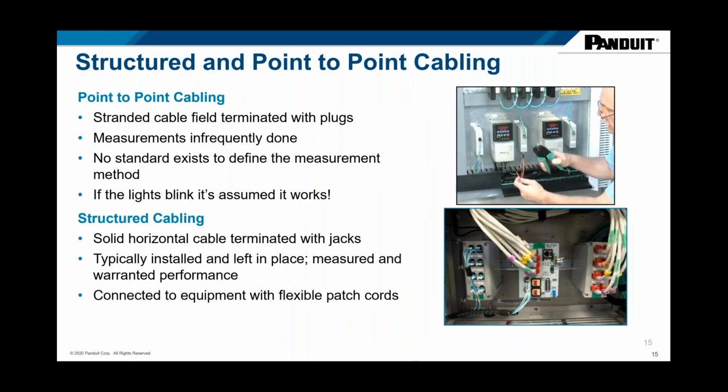All right, so I'm going to come back to the TIA model here real quickly. So both point-to-point cabling installations, and what we call structured cabling, are likely to occur on the plant floor. Using structured cabling in switch-to-switch connections is very appropriate and is recommended by the TIA 1005A, and is actually becoming more common on the plant floors. And we'll talk about why in a minute.